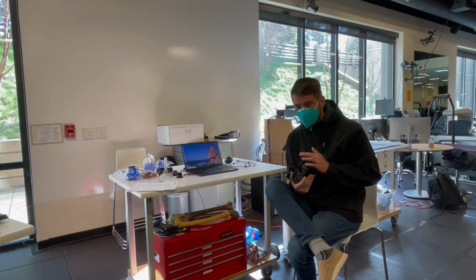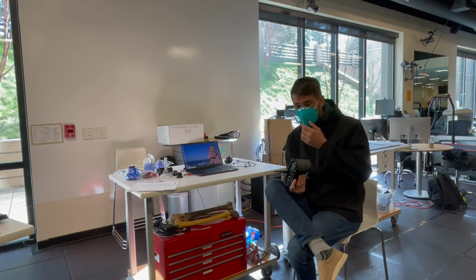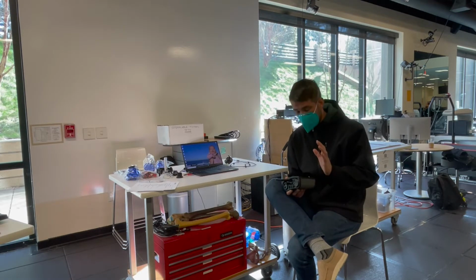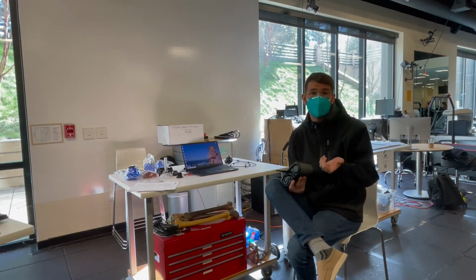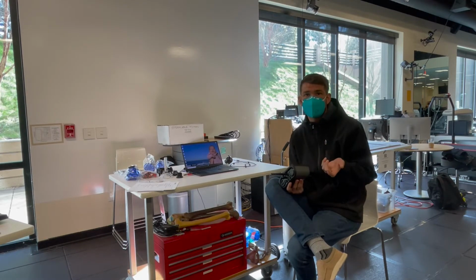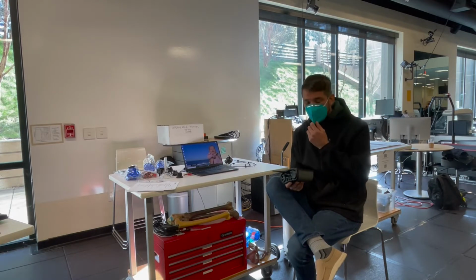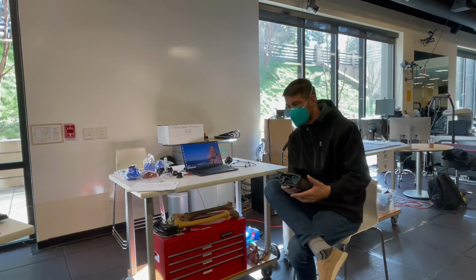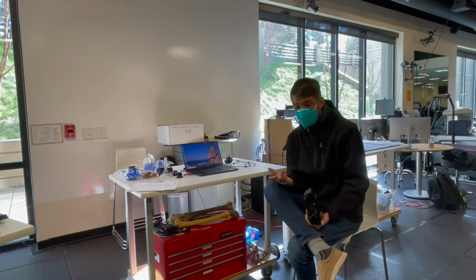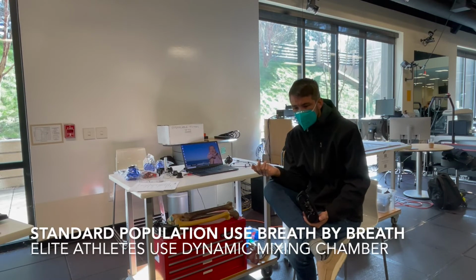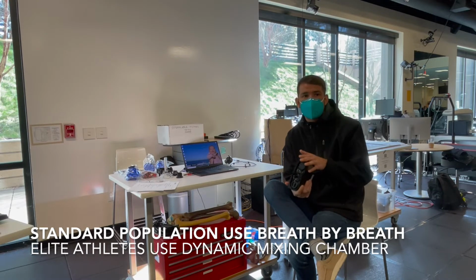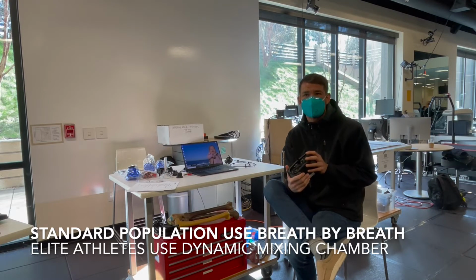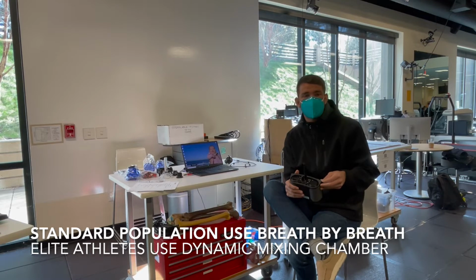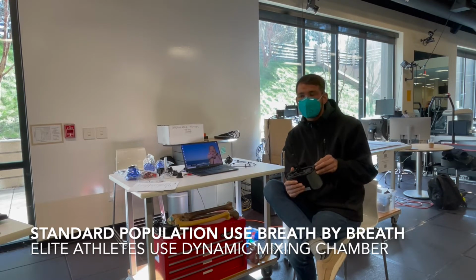The breath by breath mode is certified up to 6 liters to be within the accuracy level that we claim for the O2 analyzer being 1 to 2% and the CO2 analyzer being up to 2%. So 6 liters, and I was explaining to Julie before, my boss used to be an elite cyclist, and we were just looking at one of his tests recently. His relative VO2 was like 86 mLs per kg. It was 5.5 liters, and he was 140 pounds. That's like Olympic level cyclist, and he still wasn't quite pushing 6 liters. So you might not really run into too many people that are going to stress it that hard.